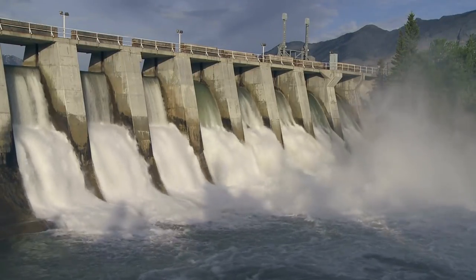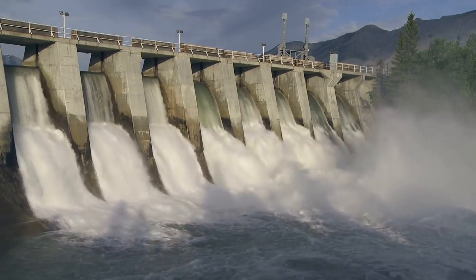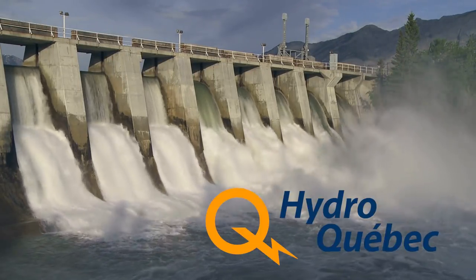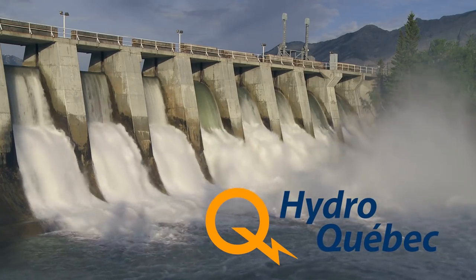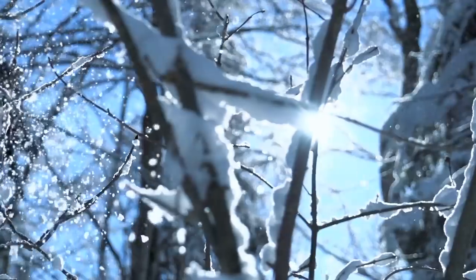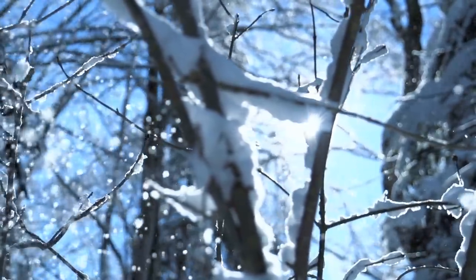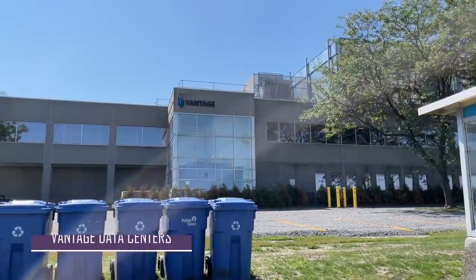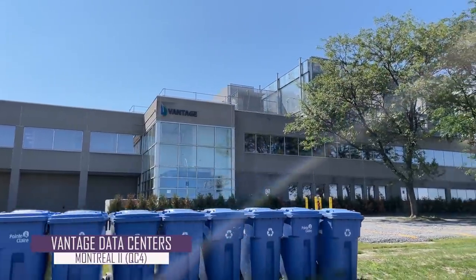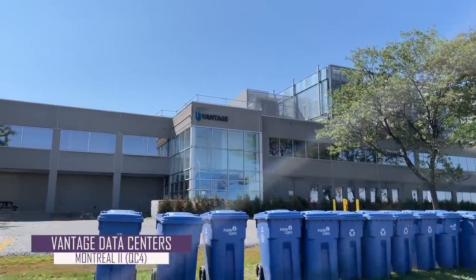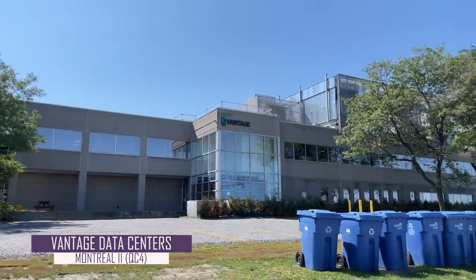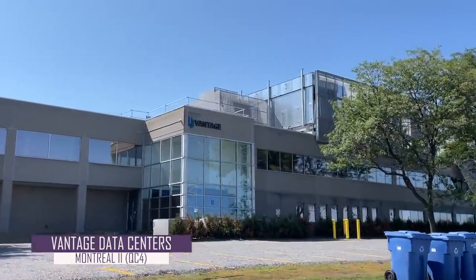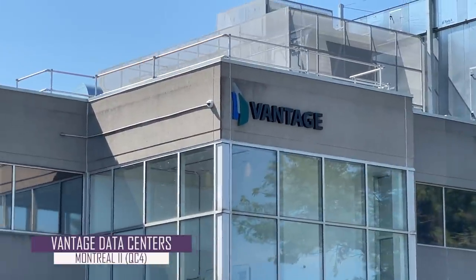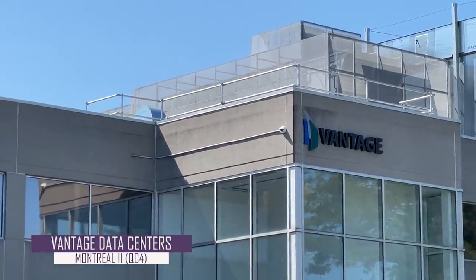Vantage's data centers operate on nearly 100% hydroelectric power, supplied by Hydro-Québec, meaning that they create very little greenhouse gas. Finally, the colder Montreal climate allows Vantage's campuses to use outside air for free cooling almost all year round. Vantage's Montreal 2 facility sits on a 10-acre site which will eventually total 3 facilities with 49 megawatts of critical IT load and 320,000 gross square feet of space once fully developed.